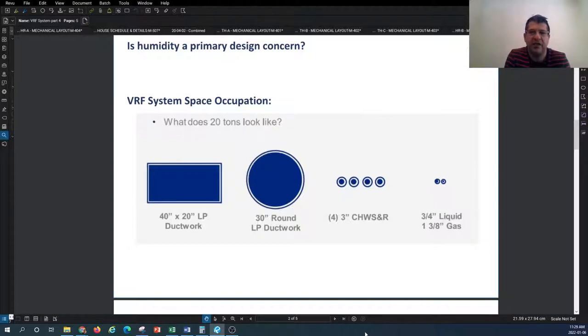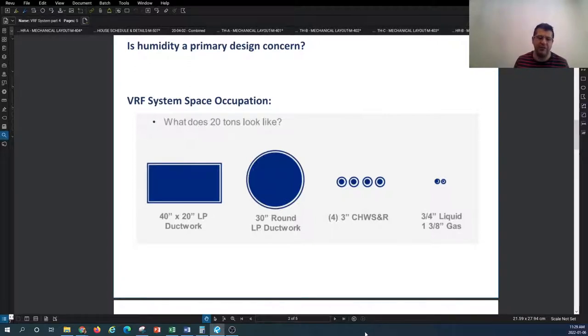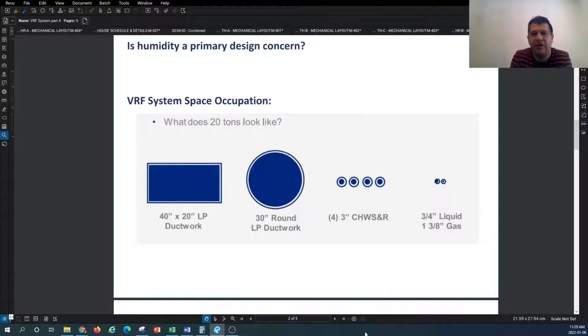For the same 20-ton cooling, you might need four sets of piping for a chilled water system — chilled water supply and return, and condenser supply and return — at 3-inch pipe size. Compare that to the VRF system on the right: you only need a three-quarter-inch pipe diameter for the liquid line and 1 and 3/8-inch for the gas line, which is very minimal space occupation. VRF gives you a lot of flexibility in maintaining maximum real estate without dedicating much space to the HVAC system.